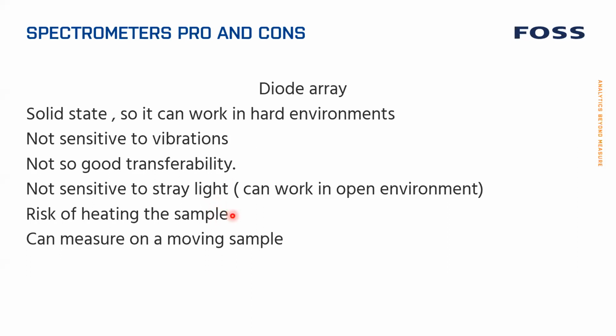There is, of course, a risk of heating the sample. So if you have a strong lamp looking at the sample, it can heat up the sample, and then you will lose moisture. It can also measure on a moving sample because it collects all the wavelengths at the same time. So if you have a conveyor belt that's moving, every time it looks at the sample, it will collect the whole spectra. While if you look at the monochromator or an interferometer, they will scan over the range, so to say, while the sample is moving, and then you will have different pictures in different parts of the sample at the different wavelengths, and that will cause some problems for you.